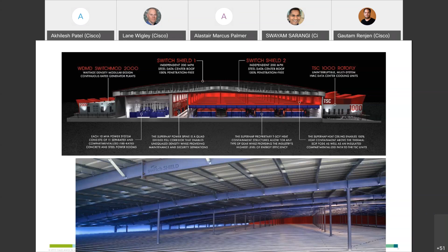There are really two benefits you could get out of liquid cooling. The first is the ability to cool really hot ASICs. If we go back just five years to the first generation of Jericho, those chips were 75 watts. If we look at what we have now with the latest Spitfire or Leaba ASICs, they can get up to 400 watts. That's starting to get very hard to cool. Maybe we can go to 500, but the heat sinks are now very, very large. So if you do liquid cooling, you can handle hotter chips. In addition, in some cases you can get more efficiency, but you may not always get that.